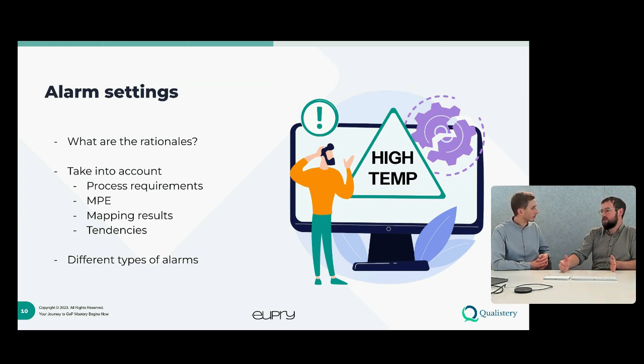Especially if we've got larger clients with, as you mentioned, a lot of different requirements and 50 fridges. If those are set in stone, that we are planning to keep this unit between 2 and 8 degrees, it's easier for individual units to use those pieces of equipment because they know what the process boundaries or requirements are. So you can differentiate between harder and softer requirements in terms of the criticality of your goods. And this also ties back into mappings, as we'll talk about in a while.